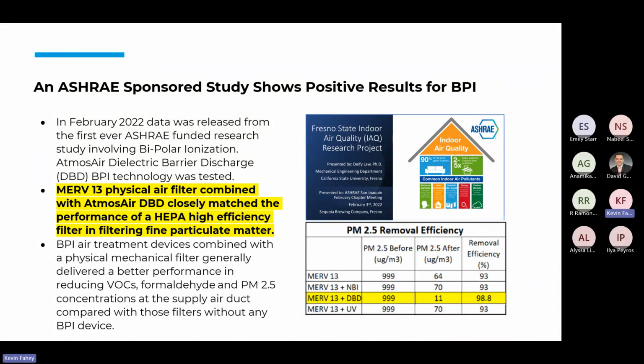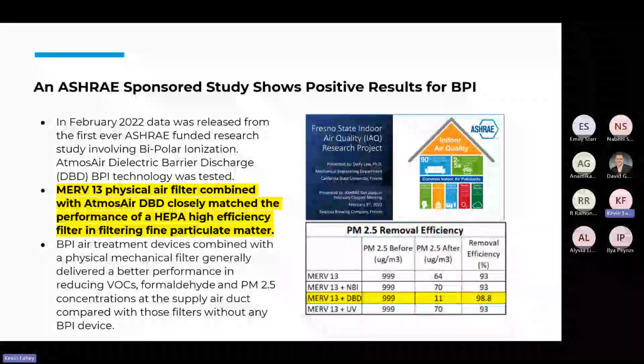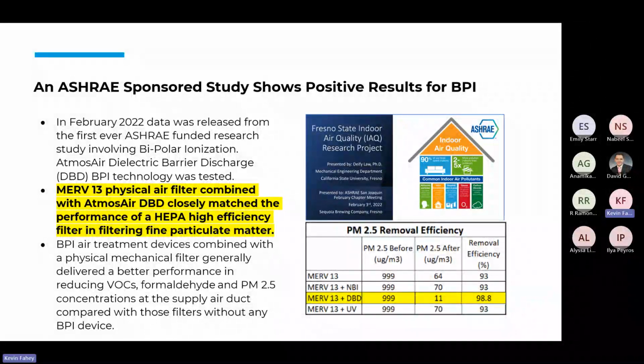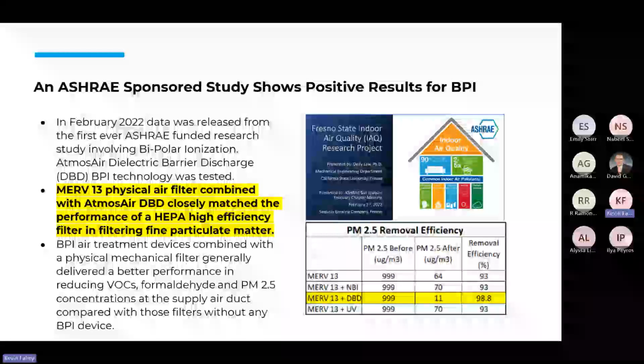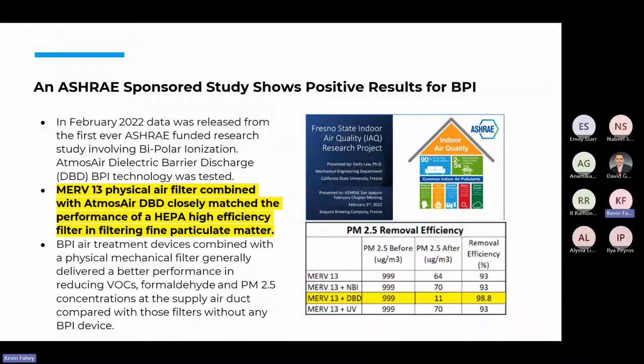And if you look at the far right of that chart, the MERV 13 baseline was removing 93%. And then the MERV 13 plus NBI, which is the needlepoint ionization, was 93%. The MERV 13 plus the tube-based, which is the dielectric barrier discharge, was close to 99%. And then MERV 13 with UV, 93%.